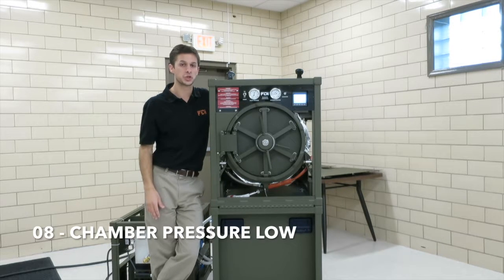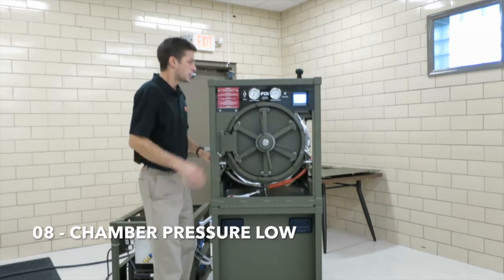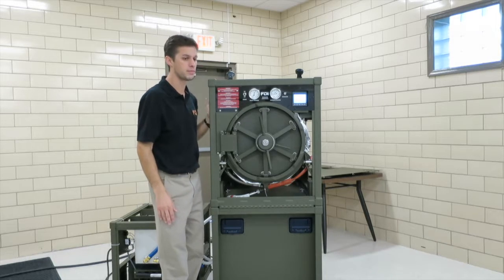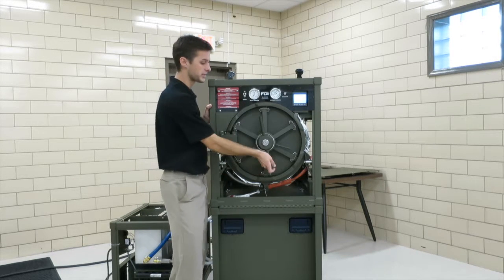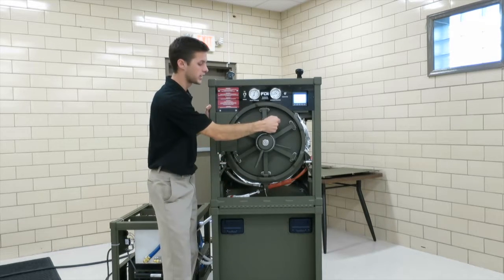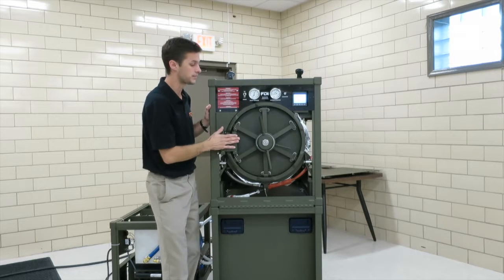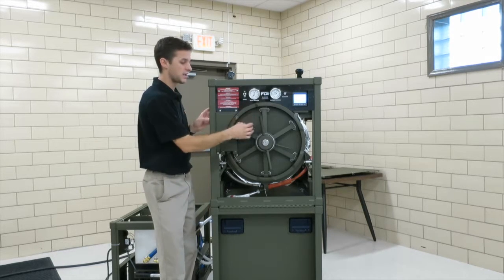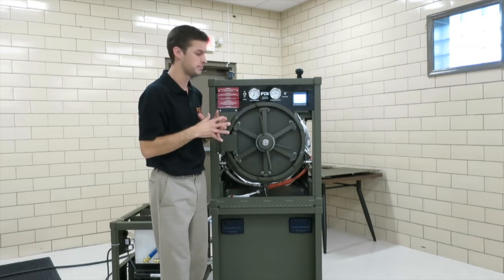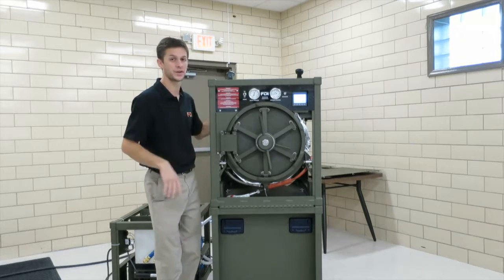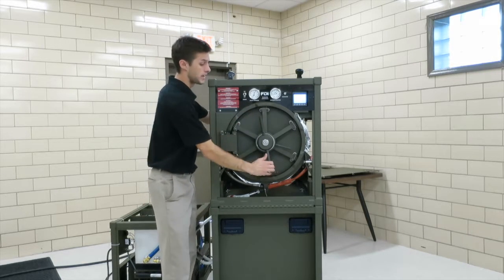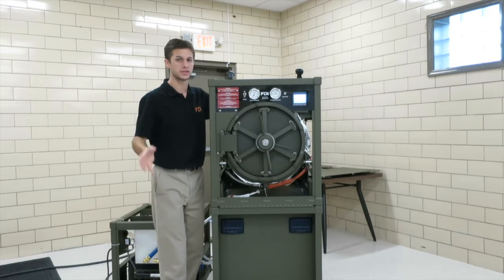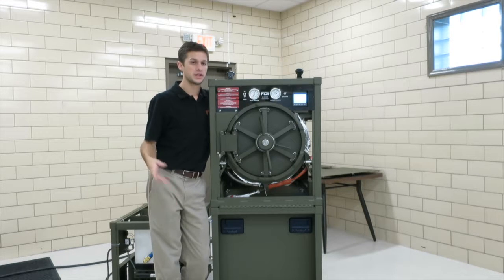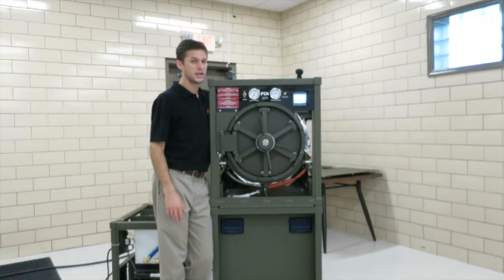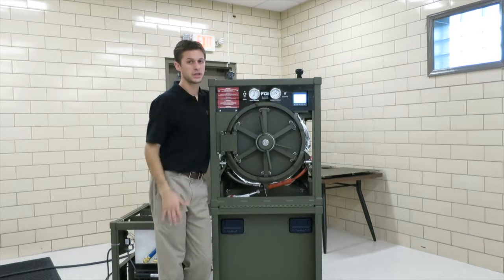Number 8 is chamber pressure low. So it could be caused by the pressure transmitter, but more than likely something else is going on. If during any time during a cycle, you could get this alarm. But what could cause it is possibly a steam leak. If the chamber cannot pressure up in time, you're going to get this alarm. So you could have one of your manual vents open. You maybe didn't tighten your door all the way. A couple different reasons. Reference your manual for all the things you can check. But the 08 chamber pressure low, again, if the chamber pressure transmitter on top reads that the value is too low, you'll get this alarm.